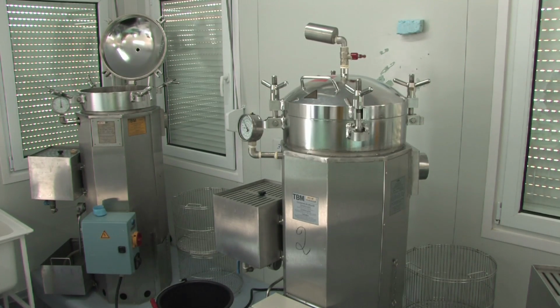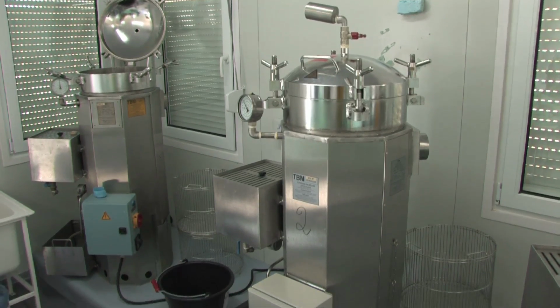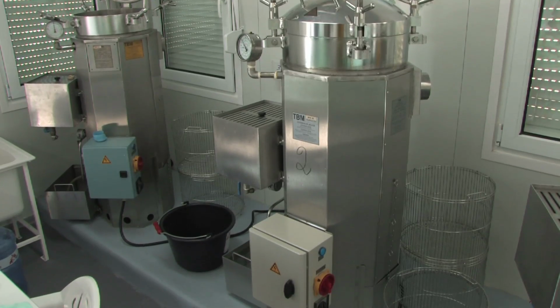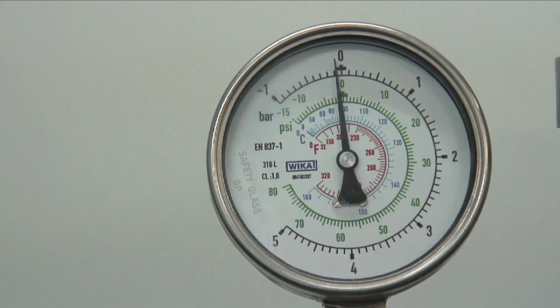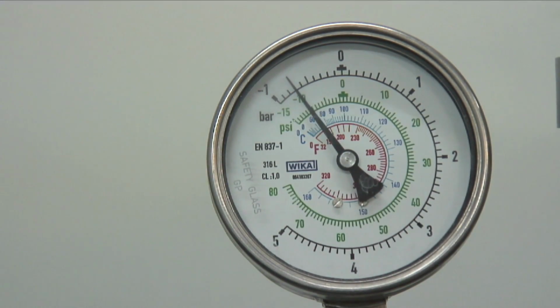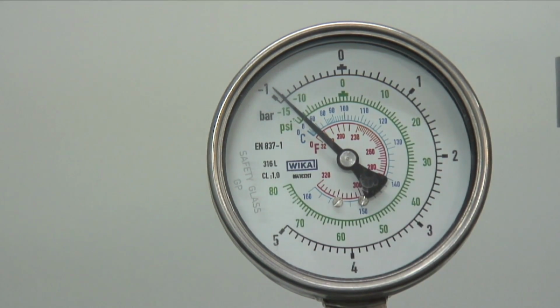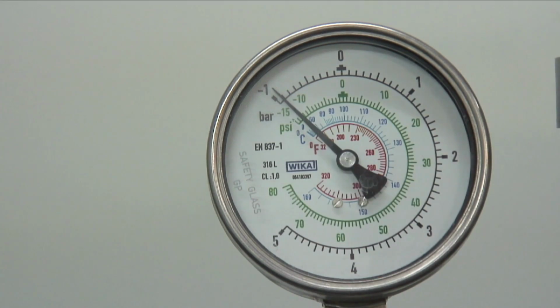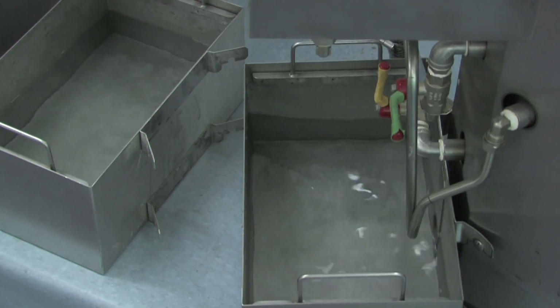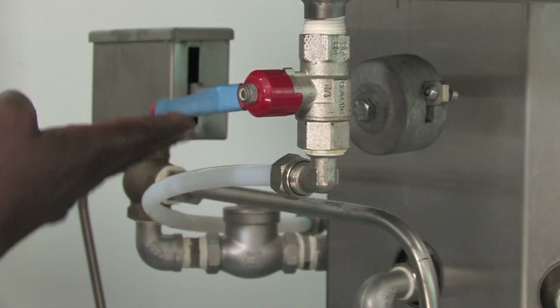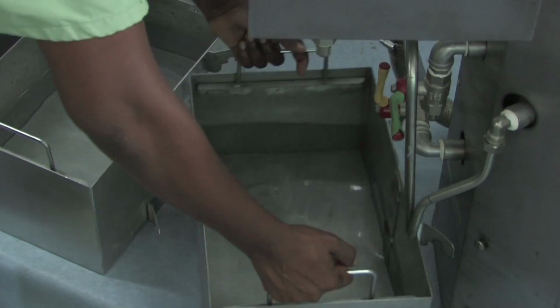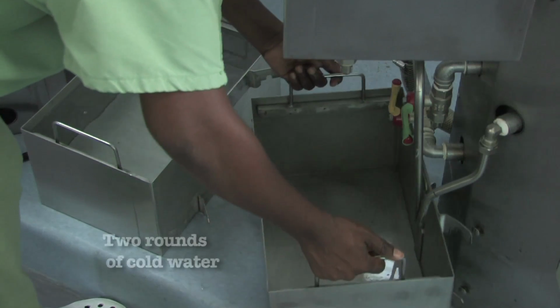Upon contact with the cold water-cooled coil, the steam in the autoclave condenses, creating a negative pressure. The pressure must drop to minus 0.9 bars. This negative pressure, combined with the residual heat, evaporates the water wetting the packs, thus drying them. When the tank is empty, close the blue valve, empty the water collection tank, and repeat the procedure.